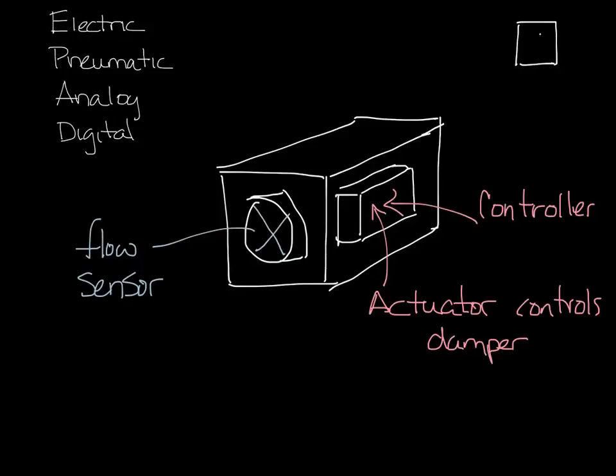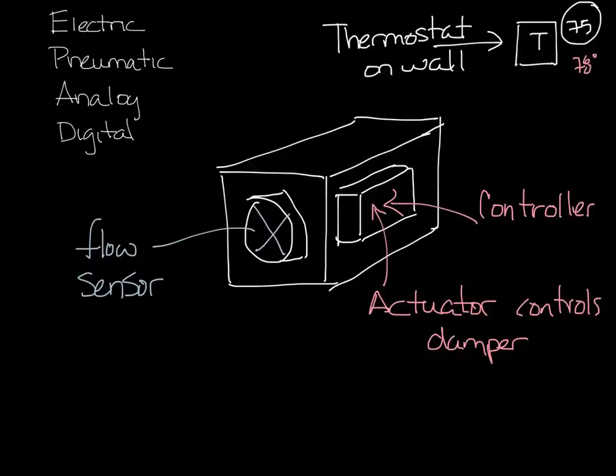Somewhere in the room there'll be a thermostat. The thermostat sets the set point and measures the room temperature. So say you have a set point of 75 degrees and your space is 78 degrees, it sends that information to the controller. The controller then says, hey we need more air and it'll send it to the actuator to open the damper.